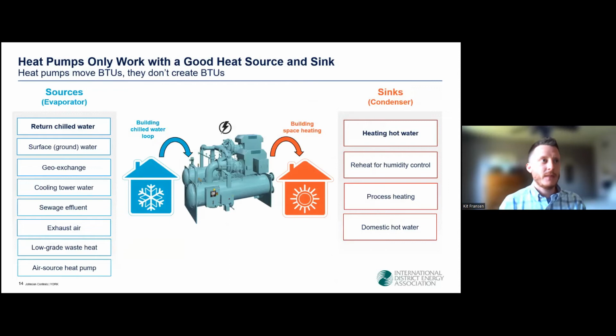Once again, heat pumps only move BTUs, or energy, so they need to have a heat source that has enough energy to support the heat sink. When these two are not balanced, or the heat pump is not sized properly, the heat pump will not operate as intended, and many will even shut down or cycle. If you don't have the ability to extract enough energy, or if you have too much energy and you can't appropriately reject it, the equipment needs to shut down.